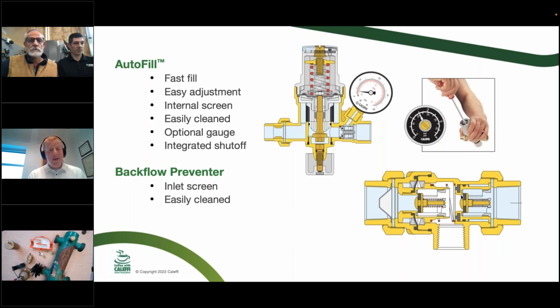And I would also say that anytime you install one of these things, make sure to not put it over really expensive pieces like your boiler, relay controls, things like that. Keep it away from things that are going to be not so happy about getting wet, is what I would say. The code tells you you're supposed to put a discharge tube down to the drain or the floor out of that. That's why it's threaded, so you can do that easily. But rarely do we see that. I mean, commercial jobs or something, it's more apt to see a copper tube placed in that and taken down to the floor.